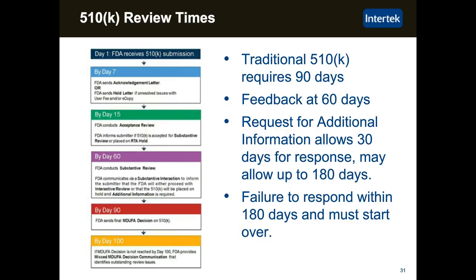Basically, the sequence goes, they receive your submission. By day 7, they send you an acknowledgement letter, or they send you a hold letter if there are any issues with the fee or the e-copy. By day 15, they'll conduct an acceptance review, and they will tell you whether or not they're going to move it forward for a substantive review or if it's placed on a refusal to accept hold. If they do accept it and it moves to substantive review, then by day 60 you're going to get some feedback. And a lot of times that feedback will be a request for additional information.